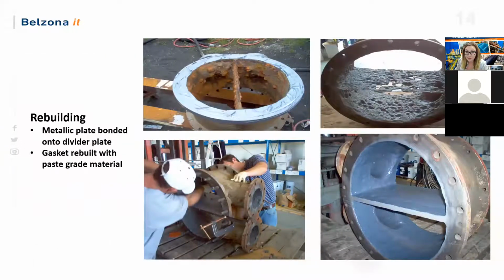A great example of needing a rebuild: this channel head we received in-house was experiencing extreme corrosion. After blasting, it was worse than originally anticipated - it looked like Swiss cheese. So what we did was reinforce the divider plate with a paste grade and remold it back to the original integrity, then applied 2 coats of our protective corrosion protection. The asset owner wasn't able to get another piece of equipment for 6 months, but we were able to return this in 24 hours.